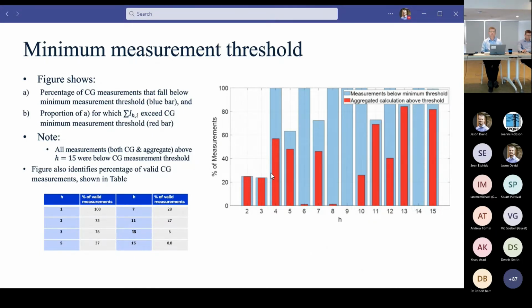And the red bar shows the proportion of measurements that fall below the collector cable threshold, for which the aggregation of the individual generated measurements actually exceeds that minimum measurement threshold. What I mean by that is, if we look at the fourth order again, we've got no measurements that exceed the threshold for the collector cable, but we've got roughly 57% of measurements from the individual generators that, when we sum them, actually exceed the minimum threshold through the collector group itself. Why this is important is that for that 57% of measurements, there is a significant amount of diversity occurring.